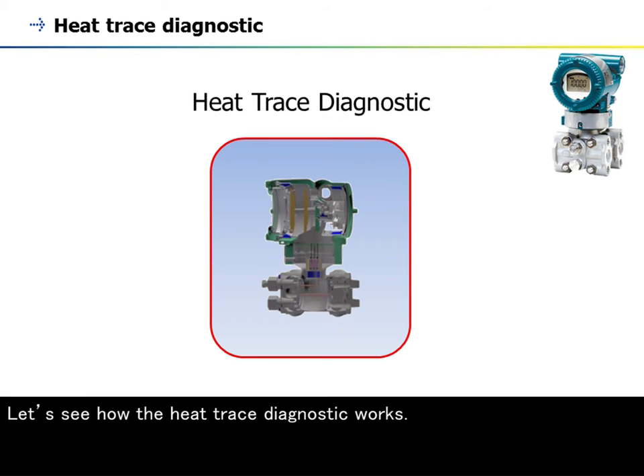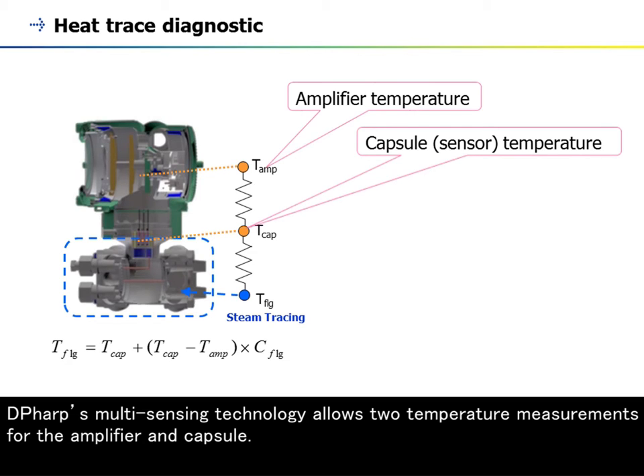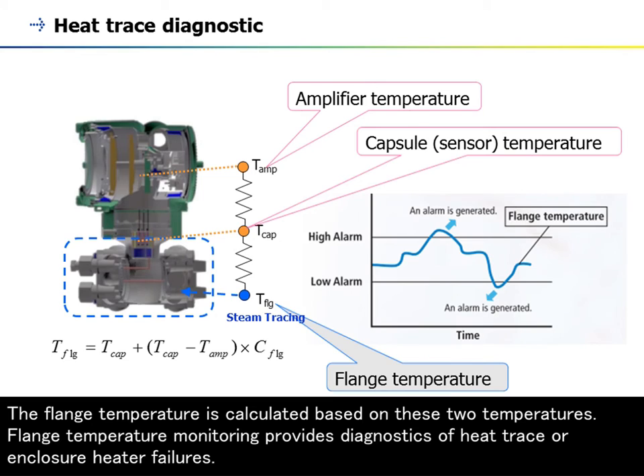Let's see how the heat trace diagnostic works. DPharp's multi-sensing technology allows two temperature measurements for the amplifier and capsule. The flange temperature is calculated based on these two temperatures. Flange temperature monitoring provides diagnostics of heat trace or enclosure heater failures.